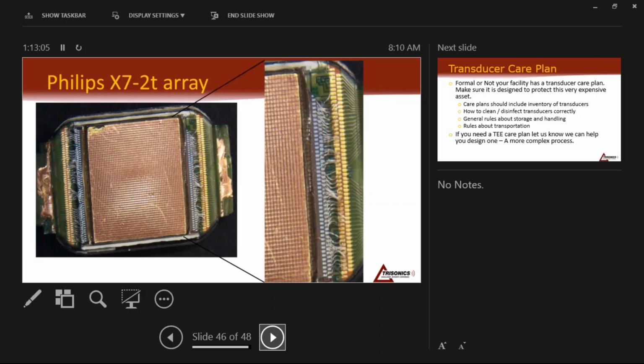So just to give you an idea, this is a Philips X7-2T array. It's a very popular TEE probe. And it's a probe that with one drop of water in the array, it ruins it. For years, we've been asking, why is that? What's going on? The reality is there are two things. A, there is no water protection in the tip of this probe. None was designed into it. But here's the reason.